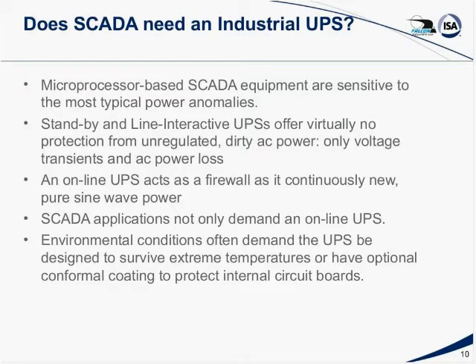An online UPS acts as a firewall because it continuously regenerates pure sine wave power, and hence does away with harmonics and most of the problems. Your SCADA applications not only demand an online UPS, they demand that it work not only in normal, what you would call office conditions, but in environmental conditions that are awfully extreme. As Mike said last time he was talking, you can go from minus 55 Fahrenheit up on the North Slope on a daily basis to above 105 degrees Fahrenheit in cabinet temperature on a daily basis. So it depends on what your environment is, what your equipment is, and your application. But yes, you need an industrial UPS.